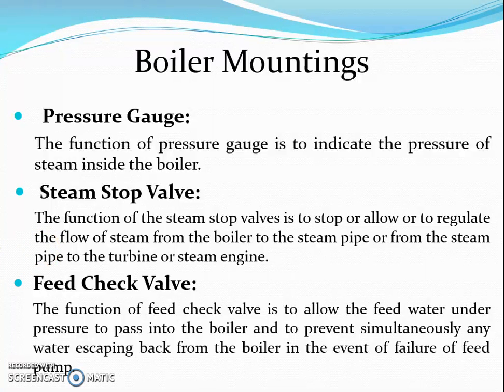The next boiler mounting is the feed check valve. The term basically consists of two verbs: one is to feed and another is to check. To feed means to provide. So it provides water to the boiler, and it prevents the backflow of water from the boiler to the feed pump in case of failure of the feed pump.